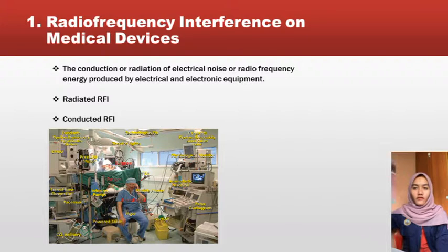There are 2 common types of radio frequency interference. The first one is radiated radio frequency interference, which is emitted directly from the equipment into the environment. The second one is conducted radio frequency interference. This is released into the AC power systems by conduction from within the equipment. The radio frequency interference passes through the power cord and then into the AC power wiring system and will most of the time affect other equipment connected to the same power network. Radio frequency signals are undesirable because they degrade the performance of electronic circuits and equipment.